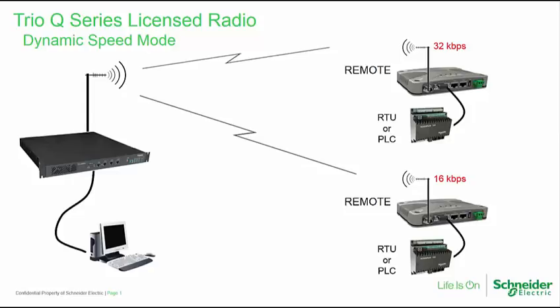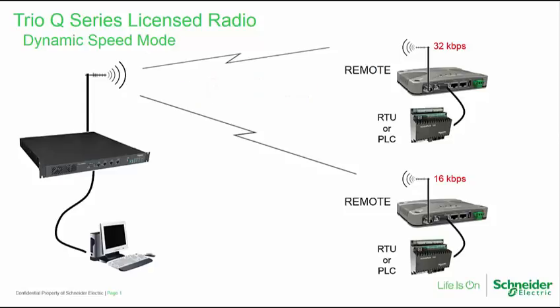Traditional narrowband data radios achieve reliable wireless communication over long distances by transmitting at low data rates, typically 9600 bits per second or less. At shorter distances, they may be able to operate at a faster data rate. However, the speed across the entire system is fixed, based upon the speed demanded by the most distant site.